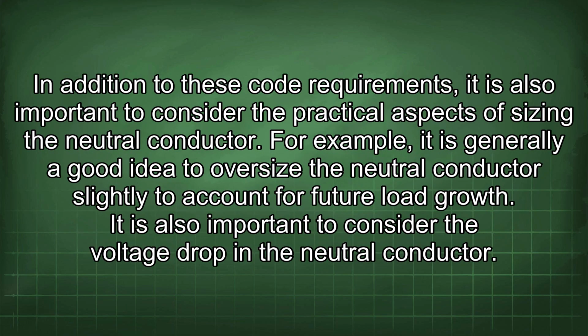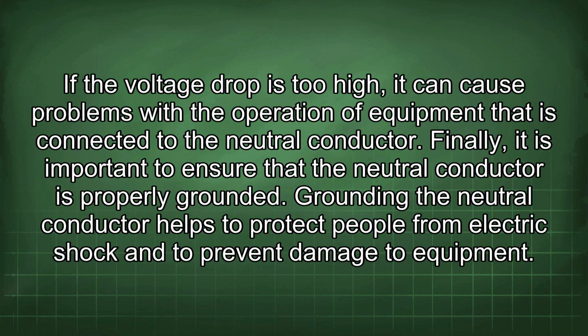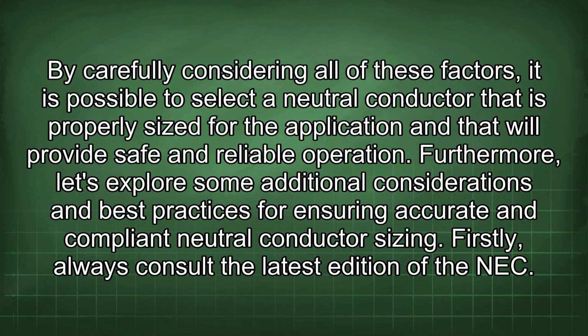In addition to these code requirements, it is also important to consider the practical aspects of sizing the neutral conductor. For example, it is generally a good idea to oversize the neutral conductor slightly to account for future load growth. It is also important to consider the voltage drop in the neutral conductor. If the voltage drop is too high, it can cause problems with the operation of equipment that is connected to the neutral conductor. Finally, it is important to ensure that the neutral conductor is properly grounded. Grounding the neutral conductor helps to protect people from electric shock and to prevent damage to equipment. By carefully considering all of these factors, it is possible to select a neutral conductor that is properly sized for the application and that will provide safe and reliable operation.